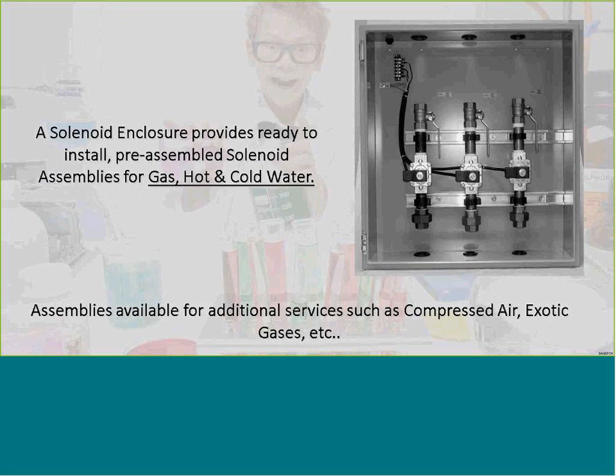A lot of the solenoids should be pre-assembled. The worst thing is having a contractor try to assemble the system out in the field. If it's pre-assembled at the manufacturer, you know the system has been tested and is ready to go. It also makes it easier for the contractor to just bring piping to and from the solenoid enclosure. The enclosure also has factory-made contacts, so you can send power directly from the control panel to the solenoid enclosure to operate the gas, water, and electric.